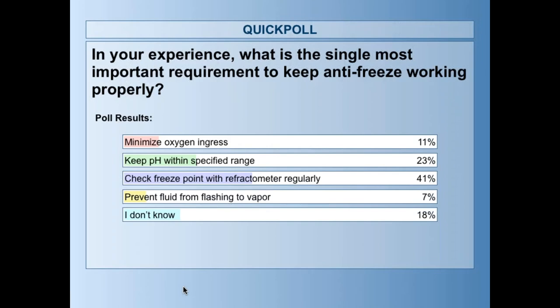I think Dow—when Kevin Connor from Dow was on here—said if you're getting into the low sevens, it's probably time to think about flushing that glycol, cleaning your system with a cleaner, and starting over, because you've used up your inhibitors and it's going to be hard to put enough inhibitors back in to salvage it back to where it needs to be, up into the 8.5 to 9.5 pH range, which is typical for new glycol.